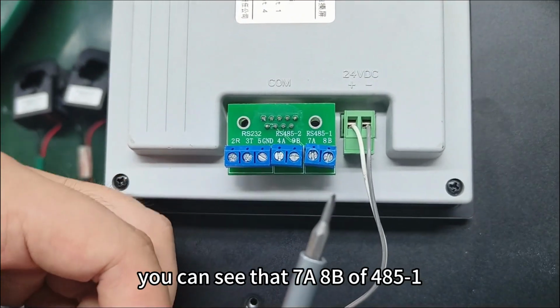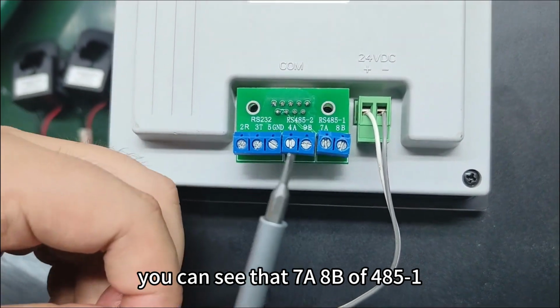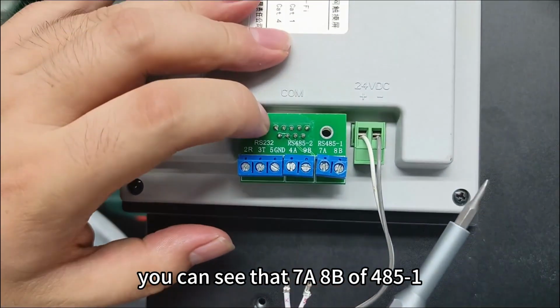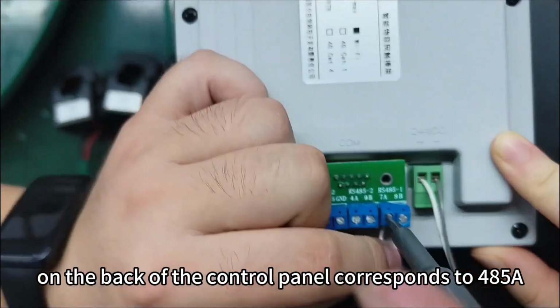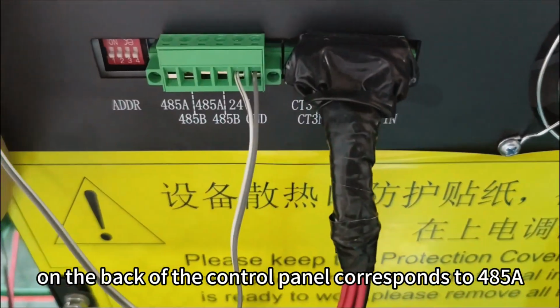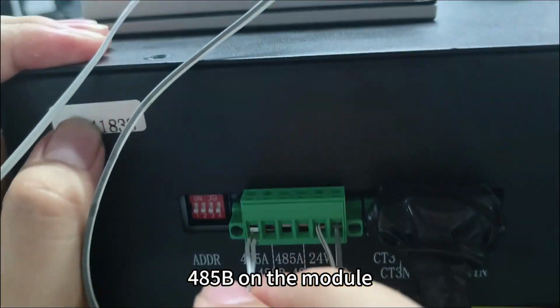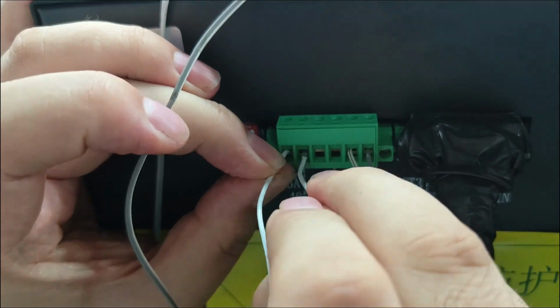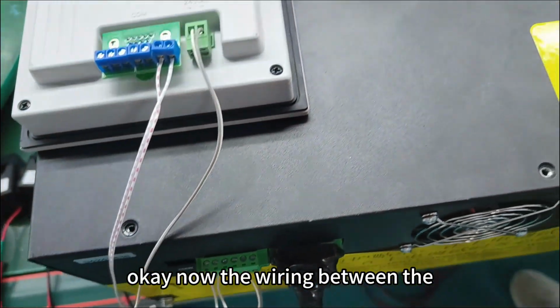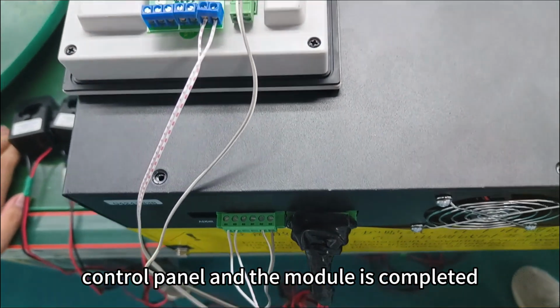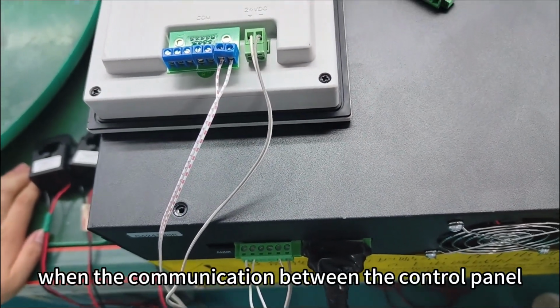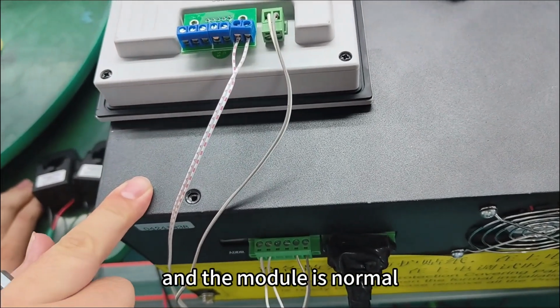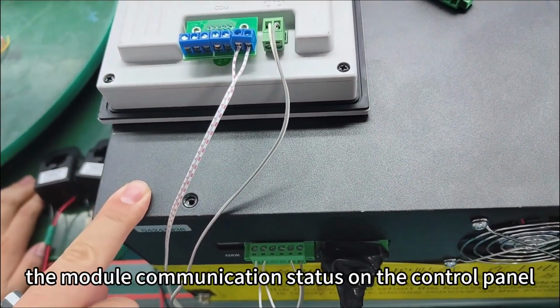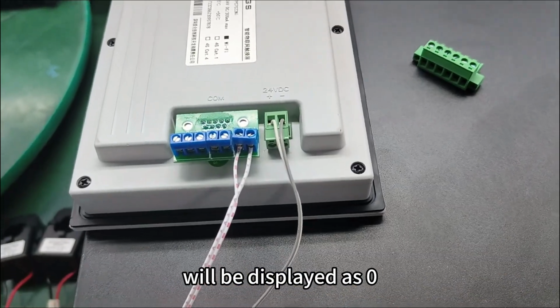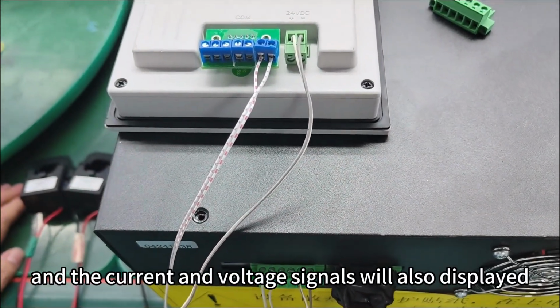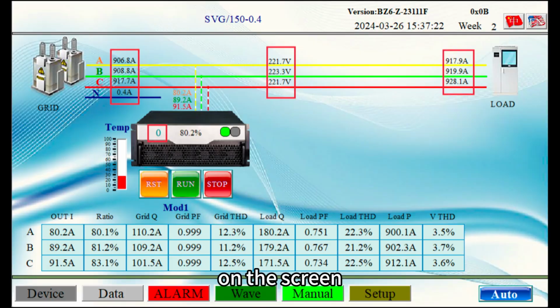Okay, next we connect the communication line. You can see that 7A, 8B of 485 1 on the back of the control panel corresponds to 485A, 485B on the module. Okay, now the wiring between the control panel and the module is completed. When the communication between the control panel and the module is normal, the module communication status on the control panel will be displayed as 0, and the current and voltage signals will also be displayed on the screen.